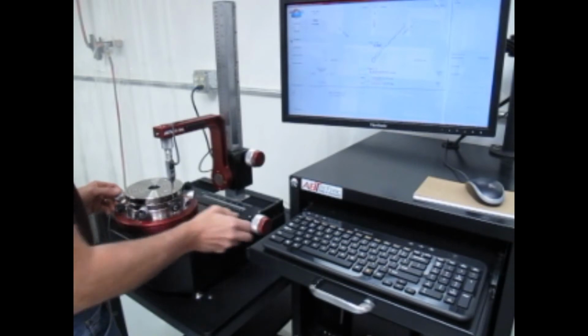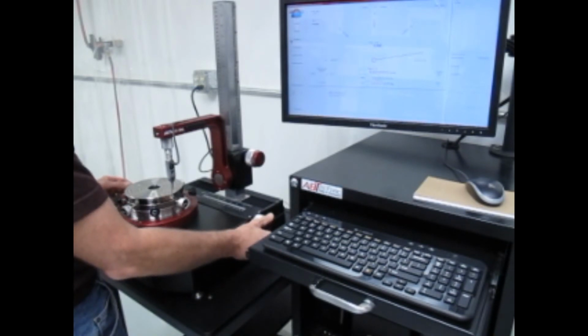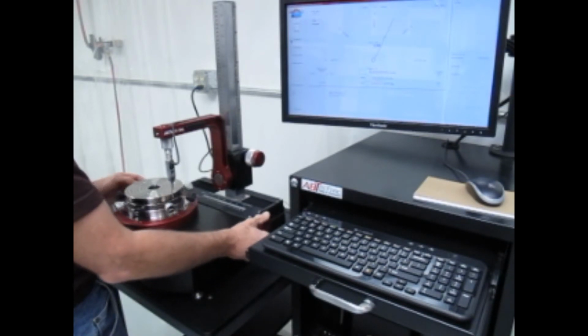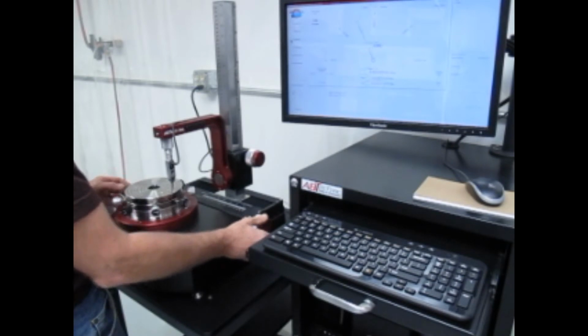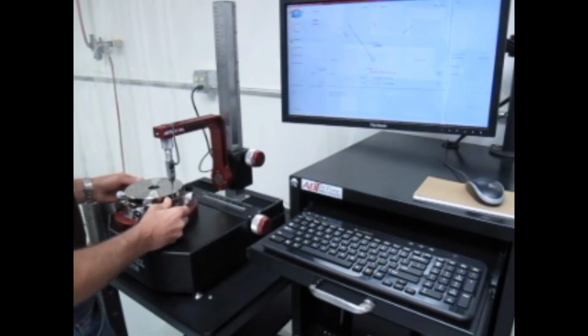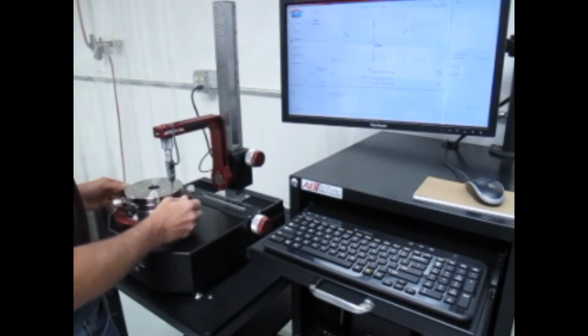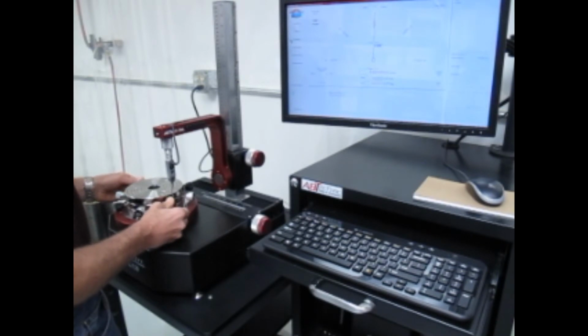but now I want to dial that in even a little better. So first I'm going to move the probe off a little bit so that I am oscillating around the zero a little better just for a visual. And then I'm going to use the tilt and center knobs again, or the C centering knobs, in line with the probe until I can get that needle to repeat, coming back to the same position with every 180-degree turn.